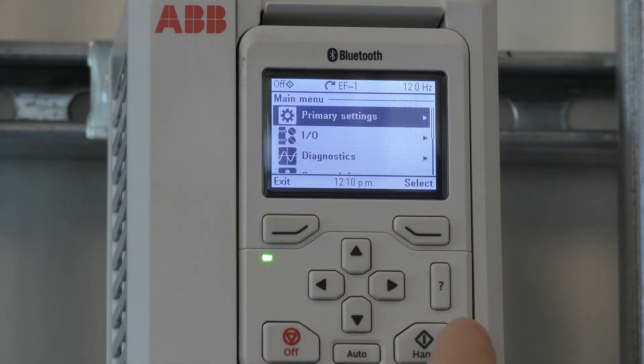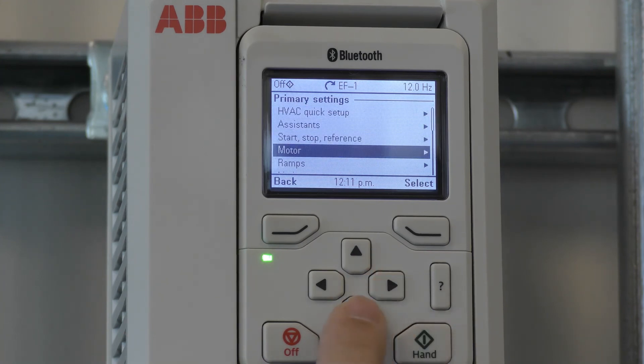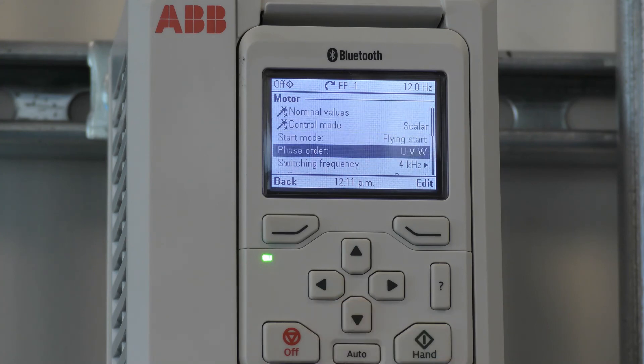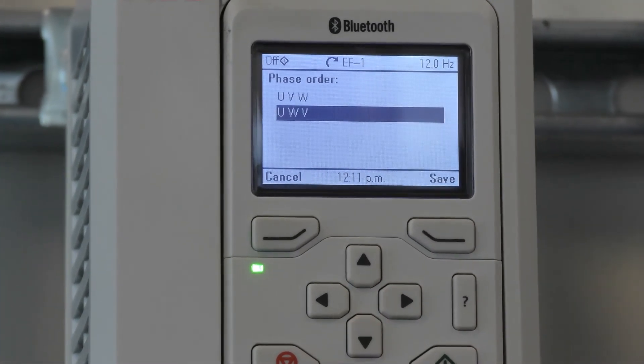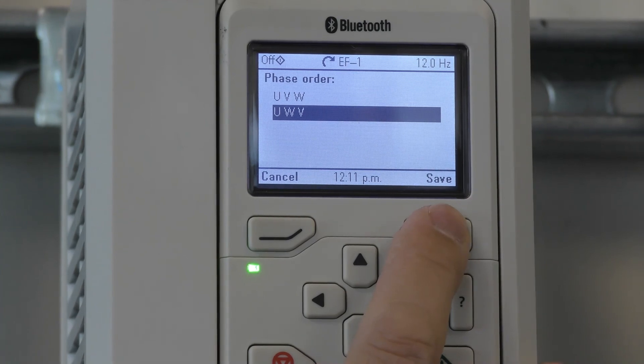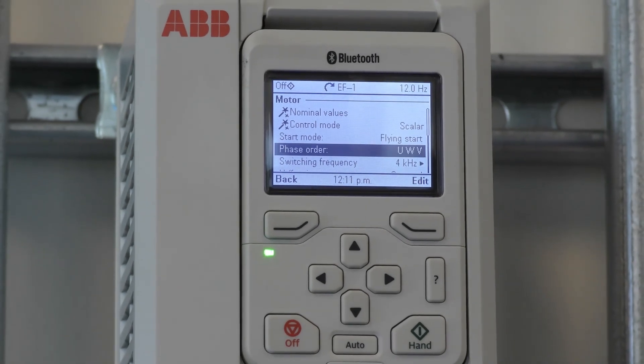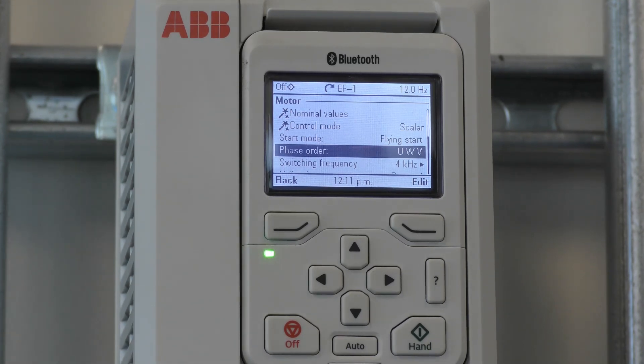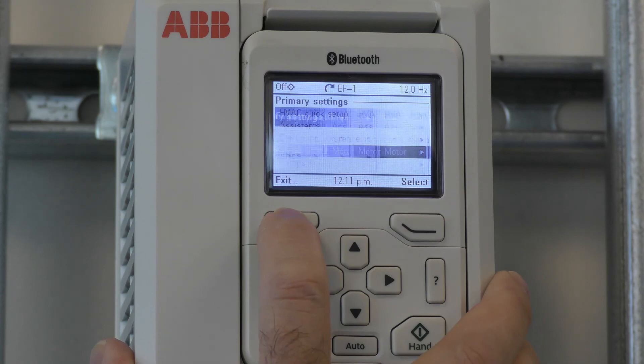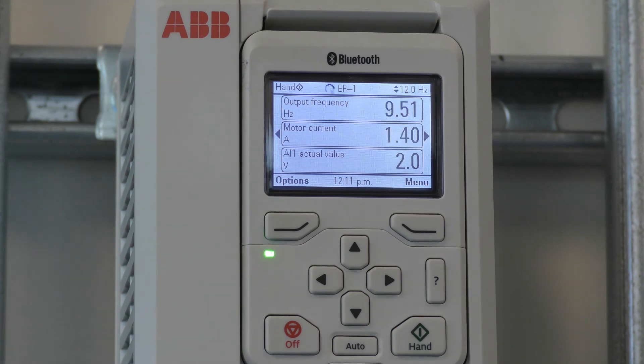Go to Menu, then Primary Settings, and scroll down to Motor, then go to Phase Order. Press Edit and select UWV. Save. This changes the phase order to make the motor go in the correct direction, so you don't have to open the cover and swap wires at the output. That completes the programming of the HVAC quick setup.